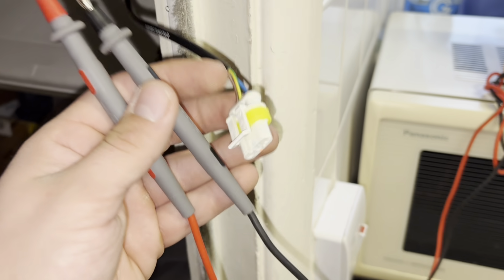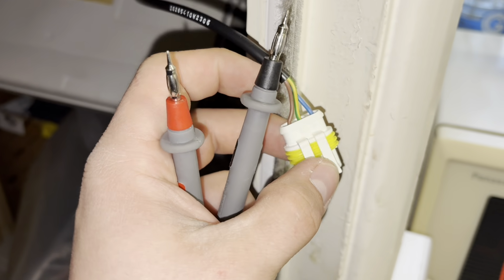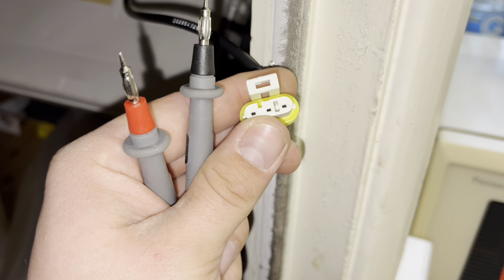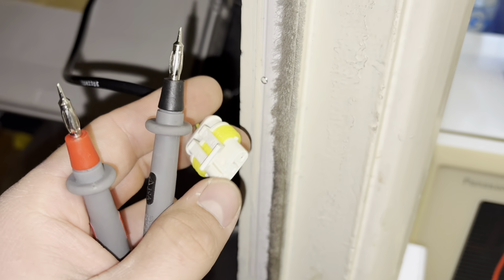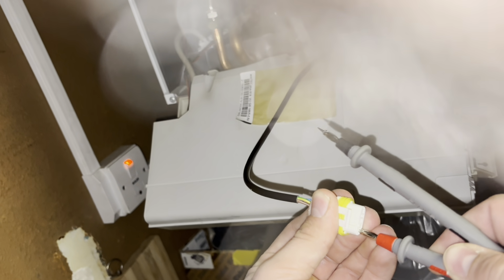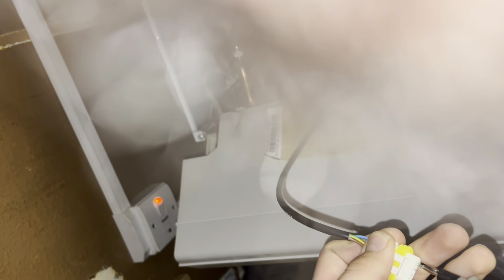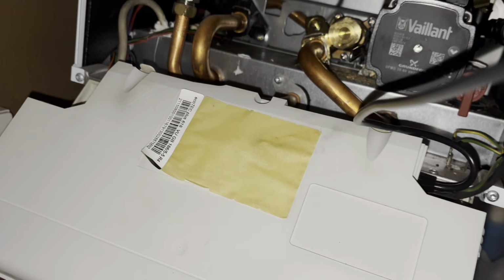How to confirm that the PCB is giving the pump power is, I would put the red probe into the brown section and then the black into the blue, and check if there's 240 volt when the pump is trying to kick in. So let me try to demonstrate that now. We will put this in there and this in there. Reset the boiler, it's probably locked out. One second. So, reset the boiler.